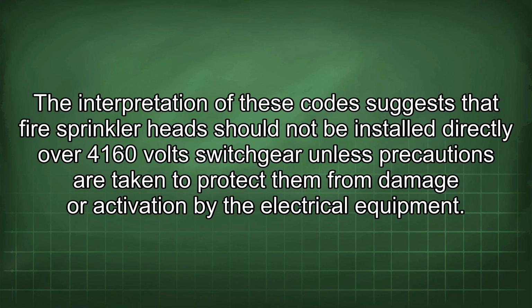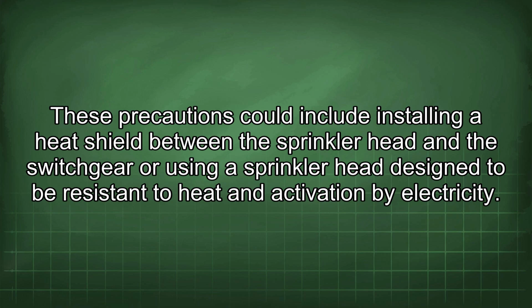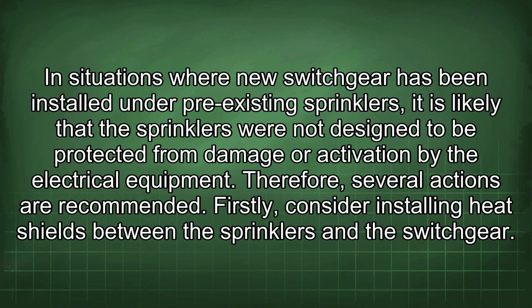4,160 volt switchgear unless precautions are taken to protect them from damage or activation by the electrical equipment. These precautions could include installing a heat shield between the sprinkler head and the switchgear, or using a sprinkler head designed to be resistant to heat and activation by electricity. In situations where a new switchgear has been installed under pre-existing sprinklers, it is likely that the sprinklers were not designed to be protected from damage or activation by the electrical equipment.